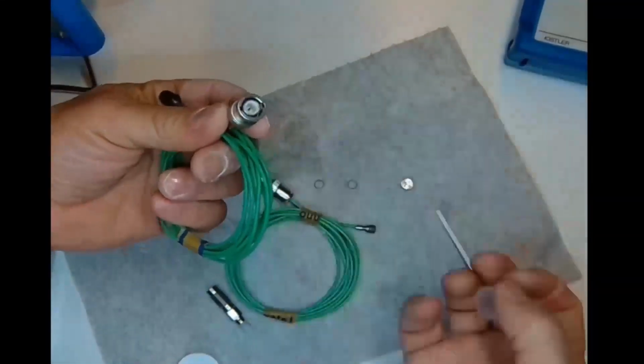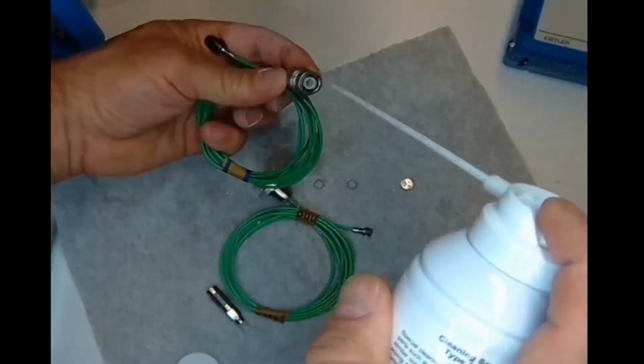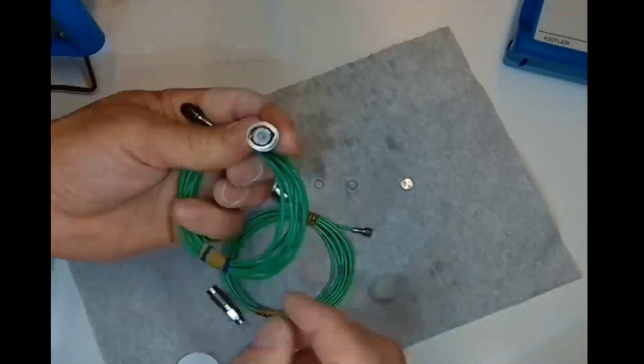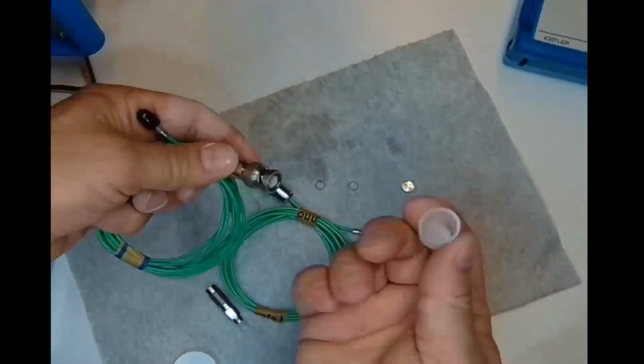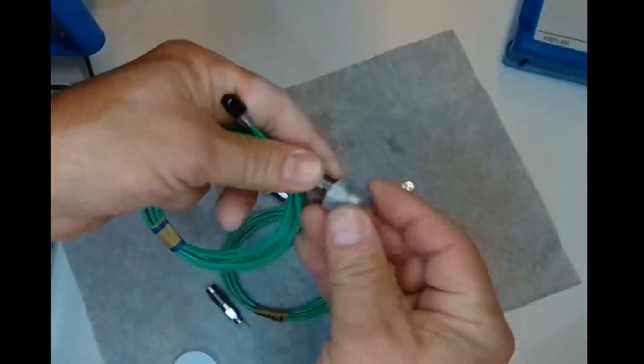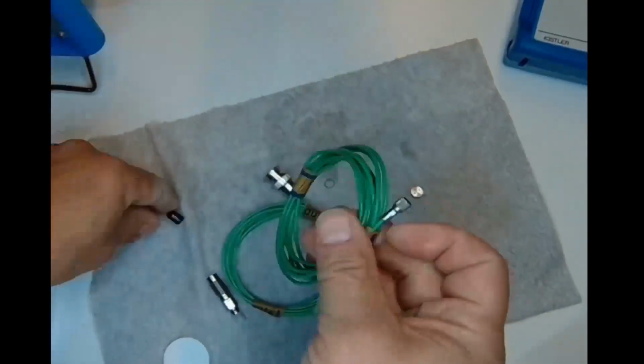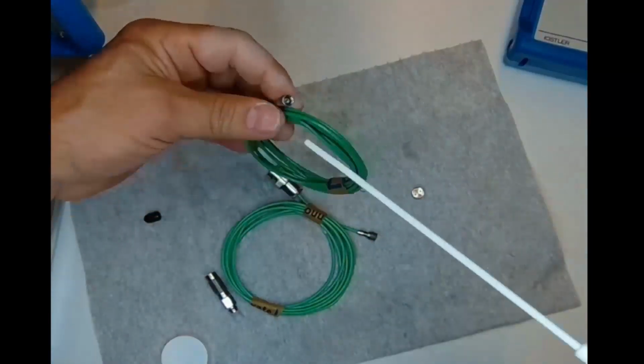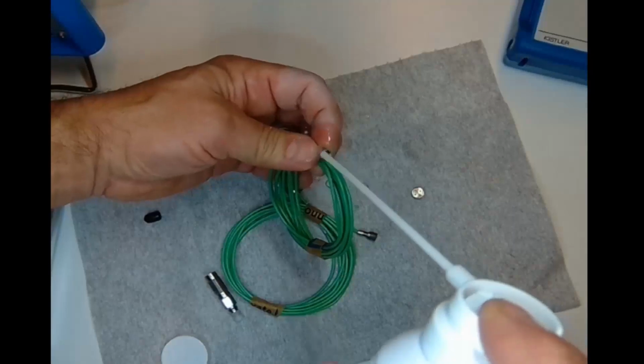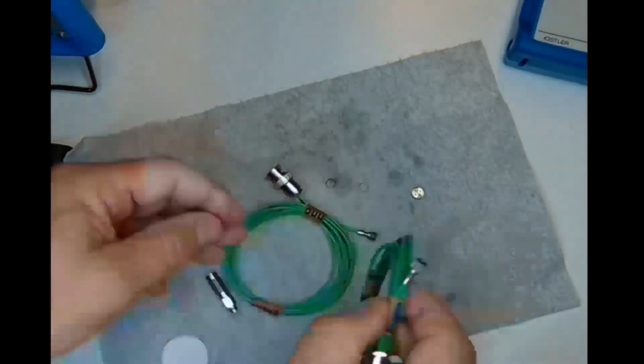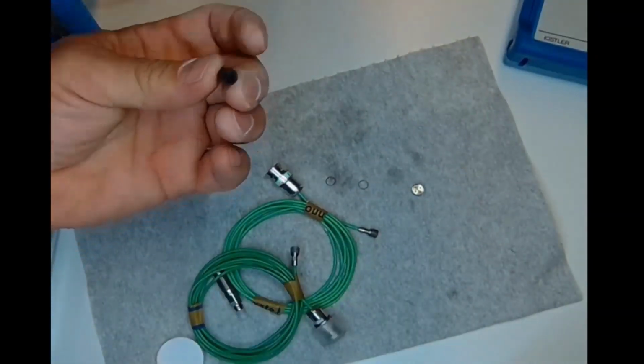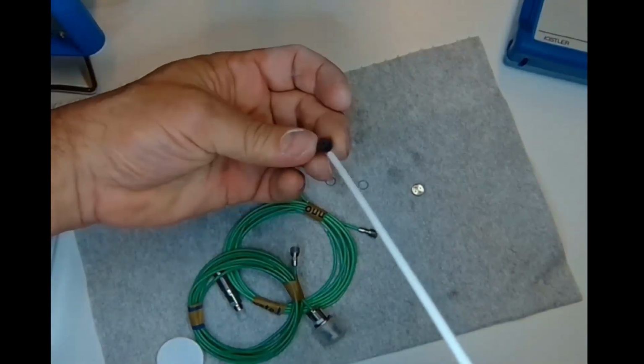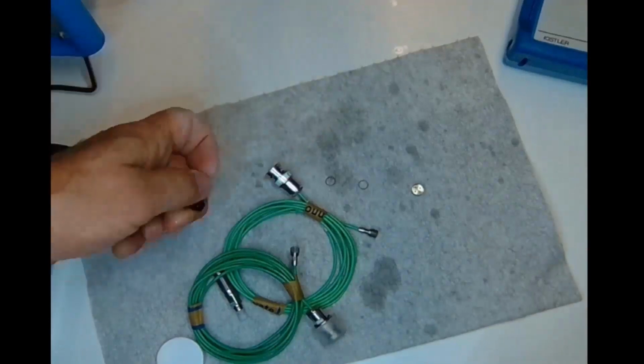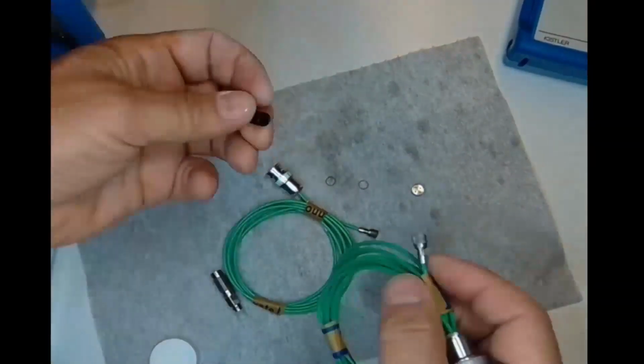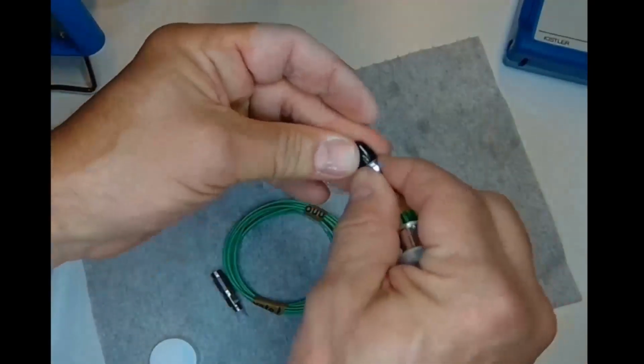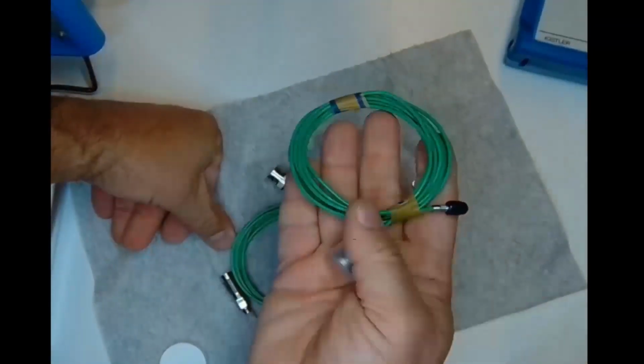For the BNC connectors, it's the same way for cleaning. Clean properly. Check visually whether it's clean or not. If it is clean, then use a clean cap and put it on. Then the smaller connector: again, use a sufficient amount of the detergent and clean it. Use a clean cap. If you are not sure, you can clean it. And after a few seconds, you can put it on. And that's it. That's the way to store your cables.